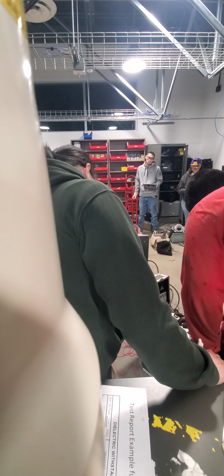All right. So we're seeing the microamps going here. So we're about 7, coming up on 10. And as I increase the kV, we're seeing the leakage current responding to it. We're coming up on 15, that's 15,000 volts, right? That's 20. No, you're reading the bottom scale, not the top. We're on the low scale.